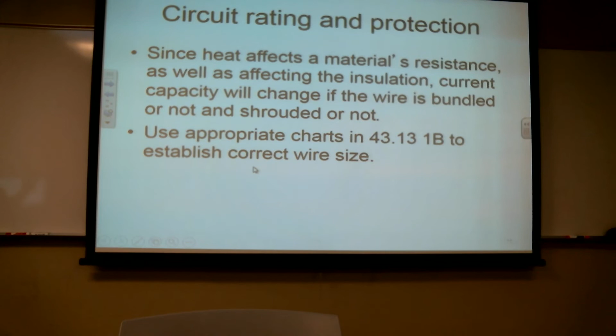So once you have a sense of what the appropriate wire size is, and the total amount of current that's going to go on that circuit to determine the wire size, you then need to go back and say, all right, what kind of current protection do I need? And there you're going to be looking in the charts and say, this circuit cannot handle more than 8 amps. I'm going to overbuild it slightly.